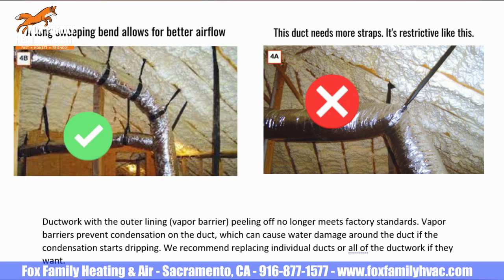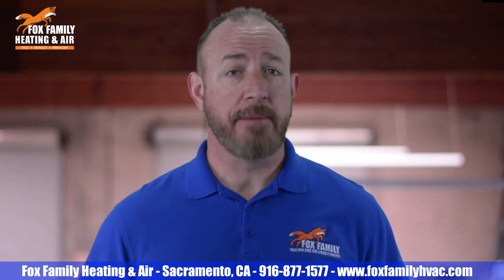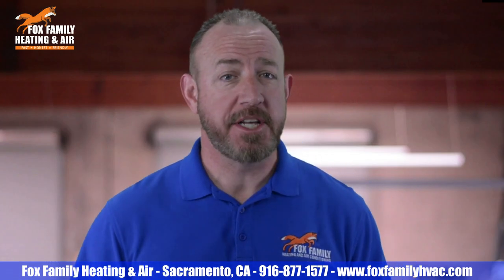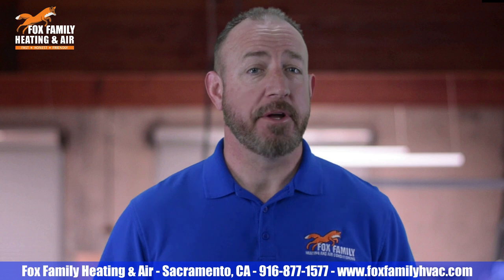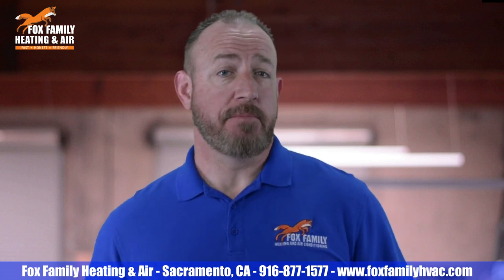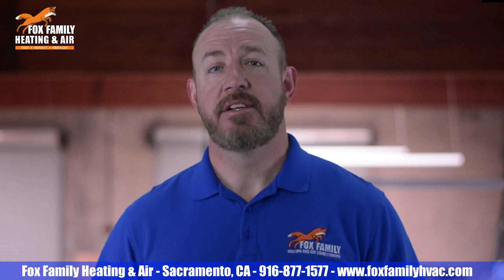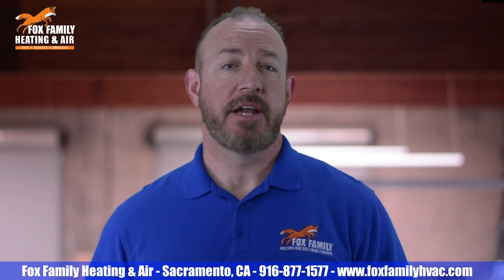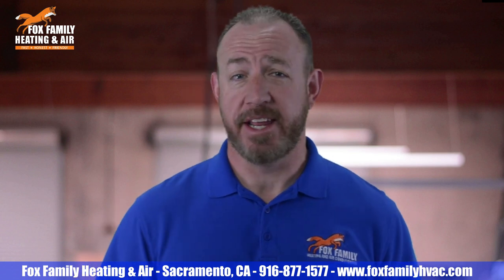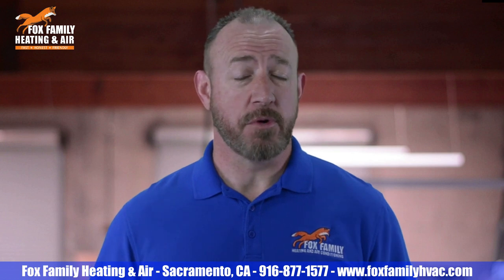If the airflow is kinked or pinched or the duct has been cut open, the air would have a harder time getting to the room. Sometimes electricians, plumbers, cable technicians, and homeowners themselves have to work up in the attic or under the house wherever the ductwork is. Those folks have been known to step on a duct and crush it. Under houses, people may have to belly crawl over or under a duct, and a duct — whether flexible or hard pipe — can be crushed or bent so much that it prevents air from moving to the room. There's no need to start fixing other things on this list if the ductwork isn't in good shape.